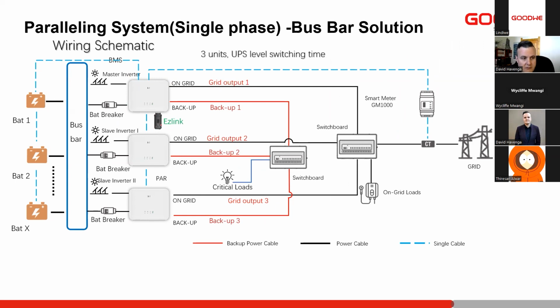There is also then configuration we do on the EasyLink, which we do not have for you today. The configuration on the EasyLink, we can just select in the scenario that it is a parallel battery bank. And then you'll see the smart meter here on the master inverter. Once they're all connected, switched on, we've confirmed on the EasyLink the number of inverters. You can see all the inverters connected to the EasyLink. Once they're all happy, all the LEDs on all our inverters should be happy. And then we can switch on the loads to backup.